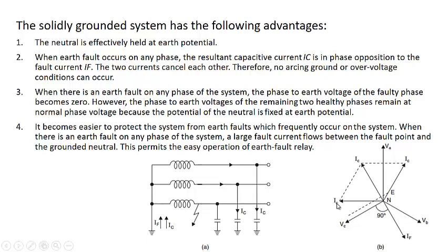Now this is current IC which is flowing through the phase A. This is current IC which is flowing through the phase B. This is the total current. You will see when the two currents, or two phasors, which are displaced by 120 degrees, are added, the magnitude will remain the same. That's why it has remained here IC. Now when the current flows, you can see from here, this will be at zero potential or ground potential, and the current flows through this. This is the fault current. That fault current will be in phase opposition to this IC, and it will try to nullify it based on its magnitude. In this case, the IF and IC will not be the same, but they are in phase opposition. So the two currents cancel each other.